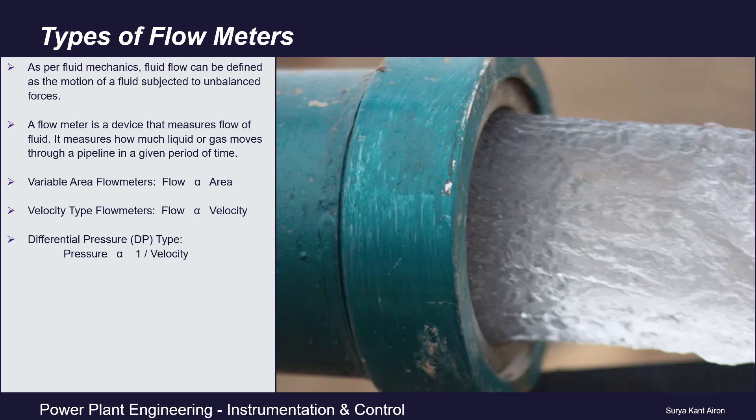Flow is equal to cross-sectional area multiplied by velocity — that is, the flow rate of a fluid equals the product of the cross-sectional area of the pipe and the average velocity of the fluid. This tells us about a direct proportionality between flow and velocity. This principle gives birth to velocity-type flow meters such as ultrasonic and electromagnetic flow meters. Also, since flow is directly proportional to area, this principle is used in variable area flow meters, that is, rotameters.